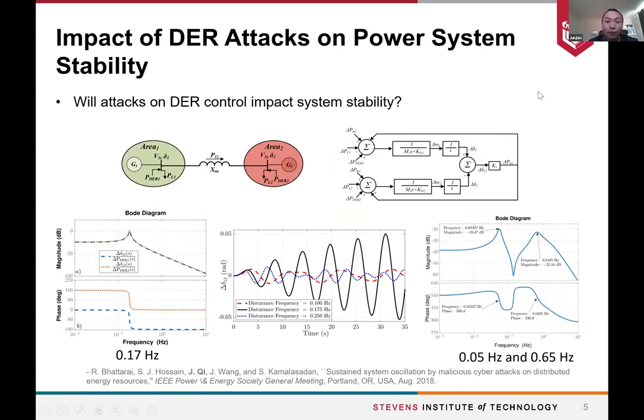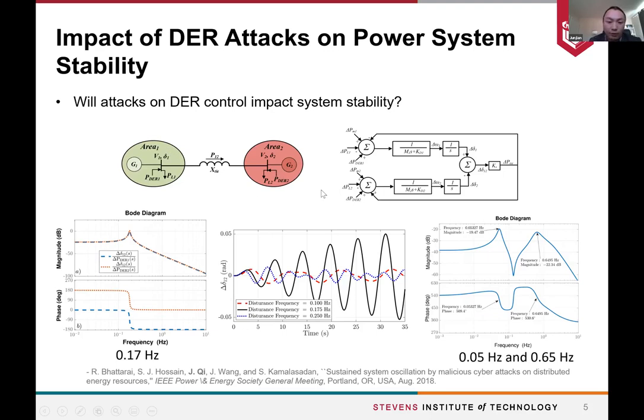One problem we looked at was whether real attacks on DER control can actually impact system stability. To answer that question, we took the Kundur two-area system as an example — commonly used for oscillation studies — and added some aggregated DERs at certain buses. Here is the transfer function where the input is the power of the DER and the output is the angle difference between buses. From the Bode diagram we can see there is a natural frequency around 0.17 Hz.